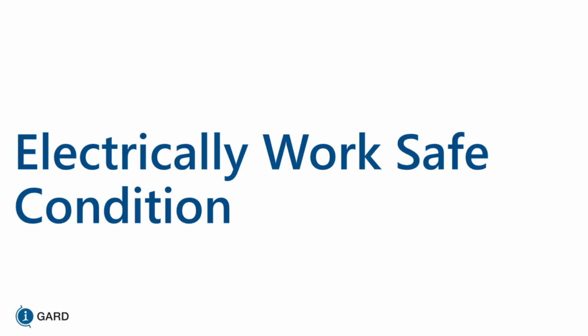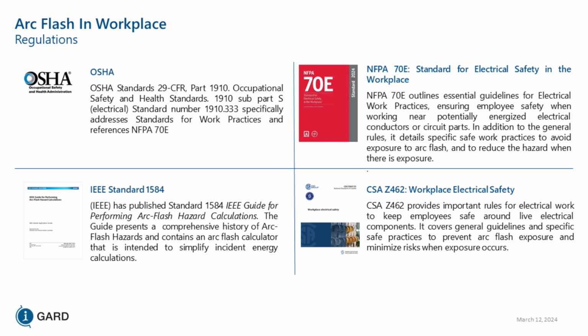So, electrical safe work condition. There's a lot of agencies that are trying to protect the workers. Arc flash in a workplace. So basically we've got OSHA and NFPA 70E in the United States. IEEE 1584 is a guide to performing arc flash hazard calculations. So you know what you need to wear to be completely safe. The clothing, it's an art form basically, because there's a lot of probabilities that someone has to look at to design the proper clothing and to approve the proper clothing.